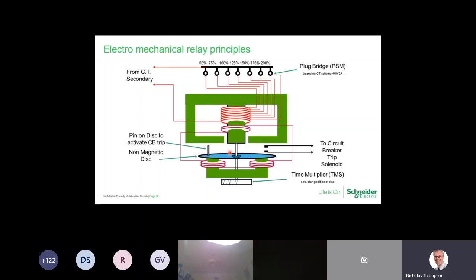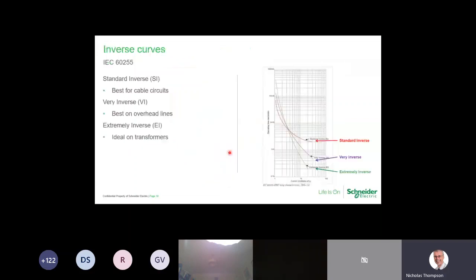And this is now bringing me into the subject of inverse curves. So if you take this mechanical example and inject a very high current into the coils driving the disc, then the disc is going to get to the trip contacts very, very quickly. But if you inject a lower current, the peg is going to get there a lot slower. So it's working on a natural curve.